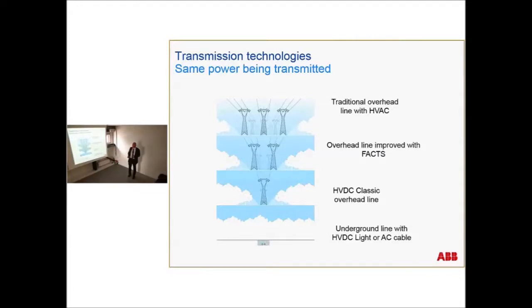Another thing is that by using HVDC, we can reduce the number of overhead lines. That means we can reduce the width of the right-of-way. For example, if we should transmit 2000 megawatt on 500 kV AC, we normally need three parallel overhead lines; with series compensation, we can reduce the number to two lines. If we go for HVDC, ±500 kV, we can have only one line. And if you don't want to see the line, you can bury it and have underground cables.